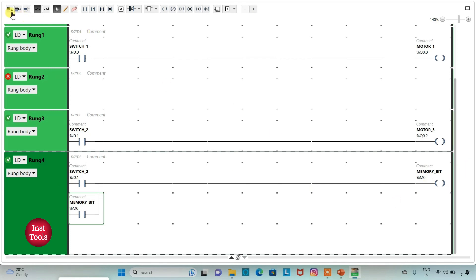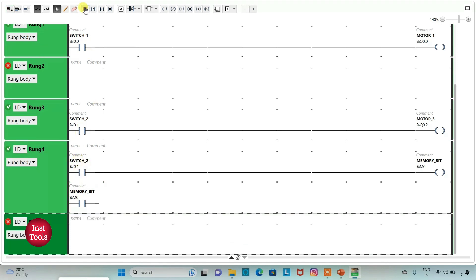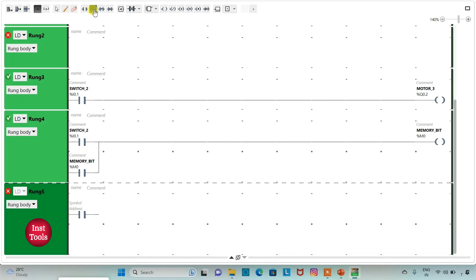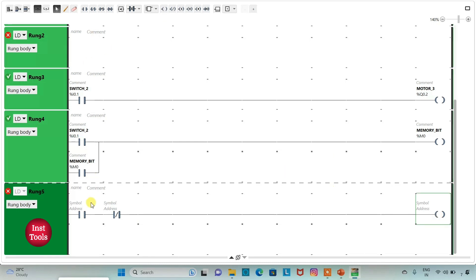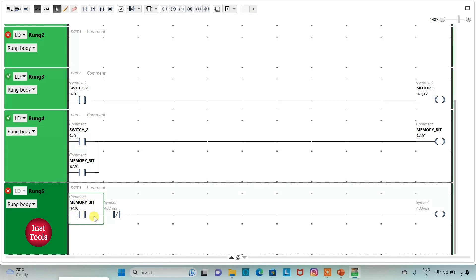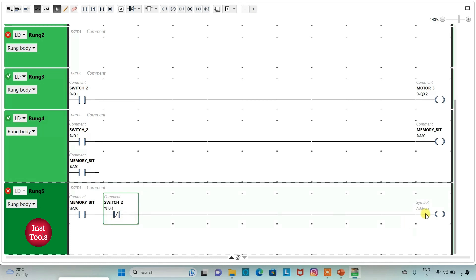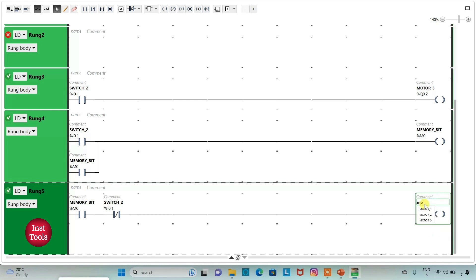Then I will add a new rung and insert a normally open contact, a normally closed contact, and a coil. I will assign address M0 (memory bit) to the normally open contact, and address I0.1 (switch 2) to the normally closed contact. I will assign address Q0.3 with symbol 'motor 4' to the coil. So when switch 2 is off, motor 4 will be on.